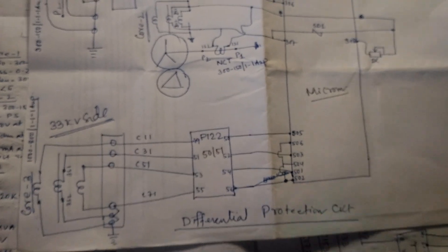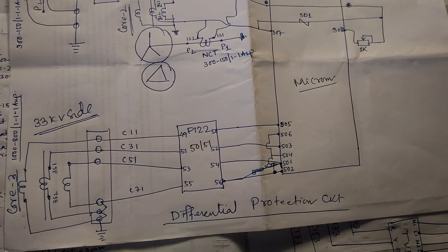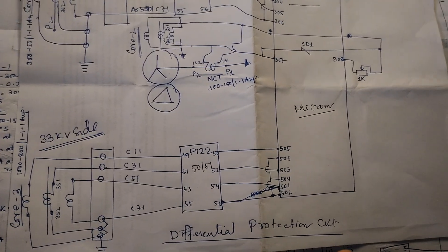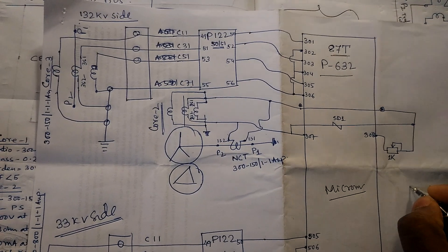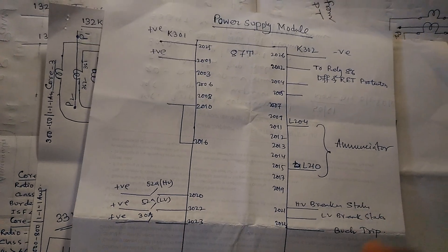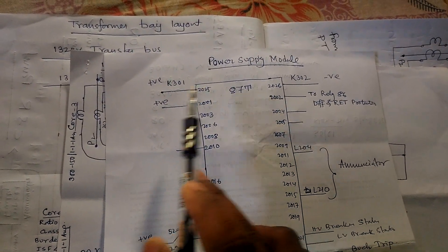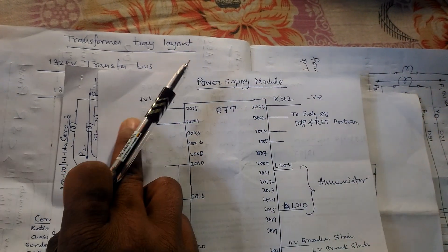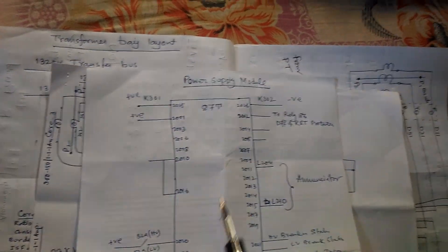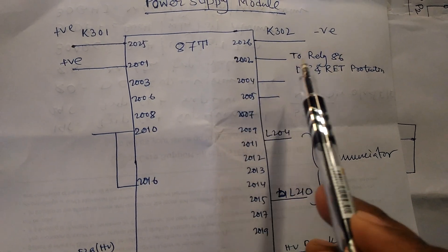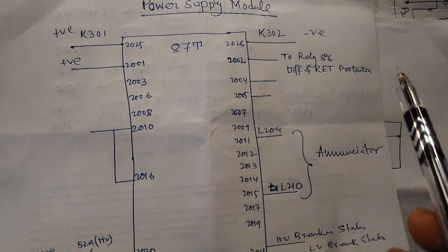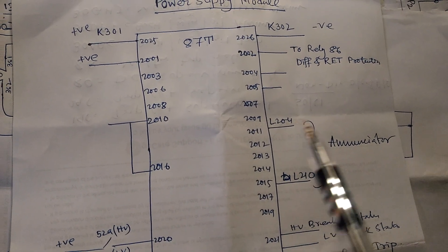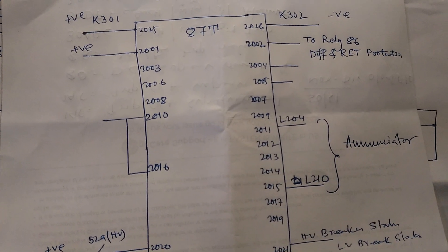We are giving power supply to the 87T relay from K301 and K302 terminals — K301 is the positive DC terminal and K302 is the negative DC terminal. The 86 differential and REF protection relay output is connected, and L-type terminals are used for the annunciators.